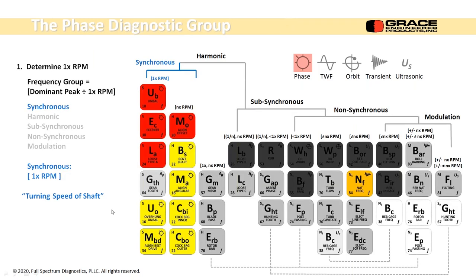On the table, these are the phase diagnostic icons. This is the group. So it's mostly synchronous problems, right? In one natural frequency. This gear problem doesn't play into it. So there's 3, 5, 10. There's 10 different phase type problems here that we'll have to dig into. They all have the same spectrum. They all have a dominant 1 times RPM, possibly a 2 times RPM harmonic, and they look enough alike that we can't tell one from the other. Okay, so if we don't do phase analysis, we're not going to be able to define any of those problems.